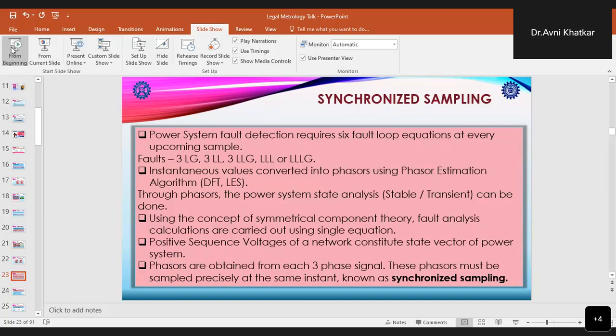So different faults can be there. 3 types of line to ground faults can be there. 3 types of line to line faults can be there. 3 types of line to line ground faults can be there, or line to line, triple line, or triple line to ground faults can be there. So all these faults can be detected in a power system by using 6 fault loop equations. And these instantaneous values are converted into phasors by using phasor estimation algorithms.